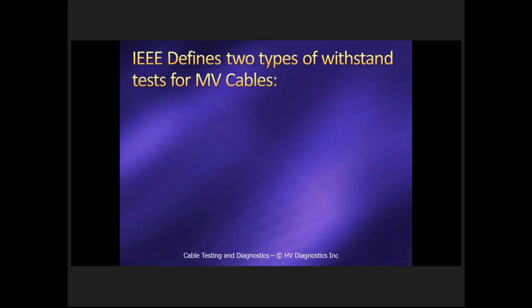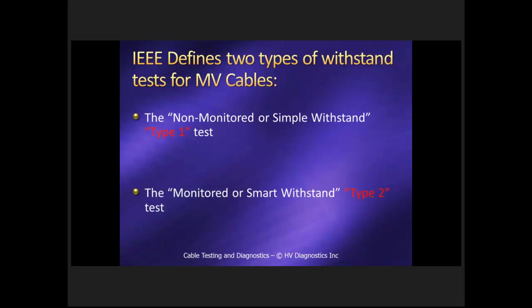As far as withstand testing of cables is concerned, you either can do a withstand test on a cable where you don't monitor too many things, it's really just a pass-fail type test, or you can monitor a condition. Doesn't matter, partial discharge, tan delta, any form of diagnostic parameter that you monitor during the withstand test, which is a smart withstand or a monitored type 2 type test. I'm not too sure where the terminology type 1 and type 2 came from. It's a bit odd, but in any case, that's what's in the IEEE 400 document.